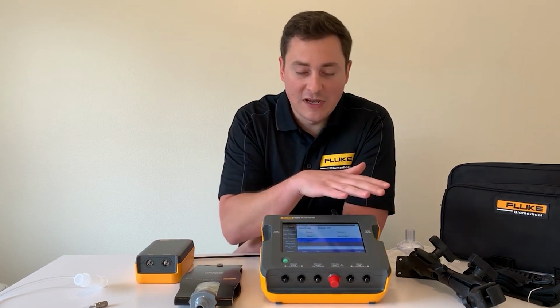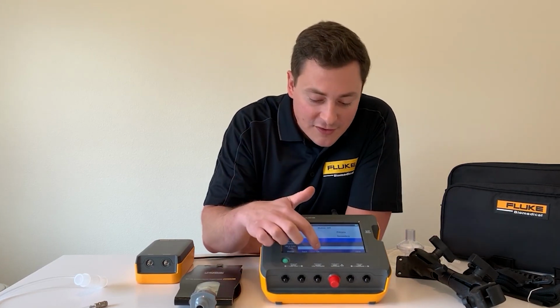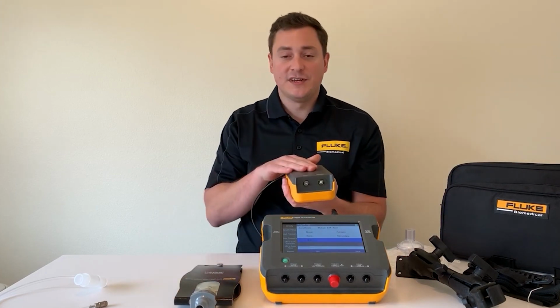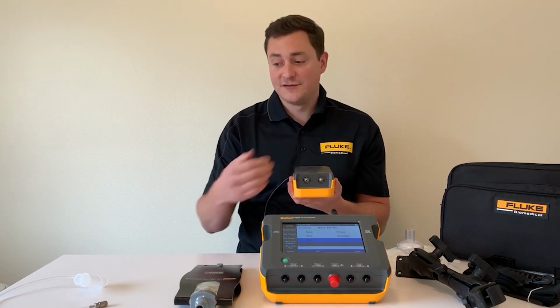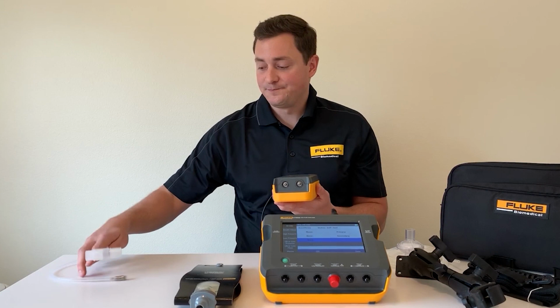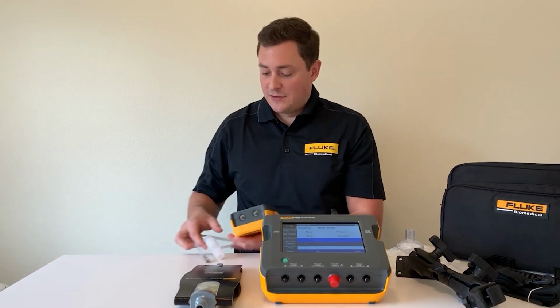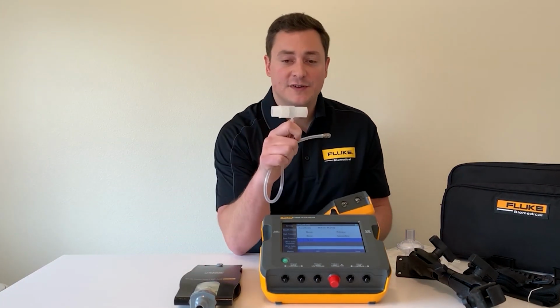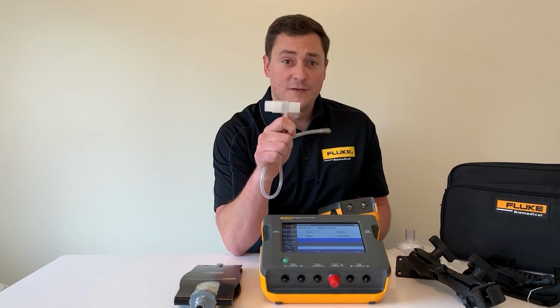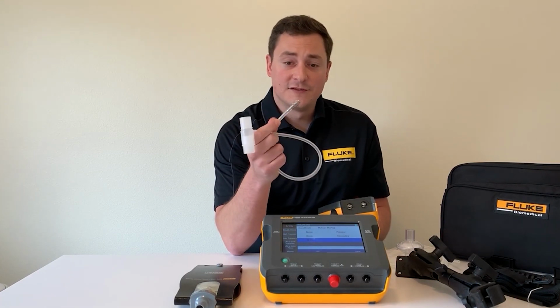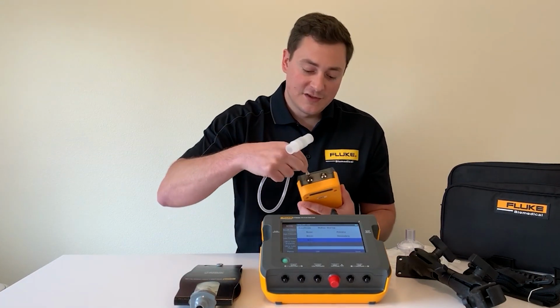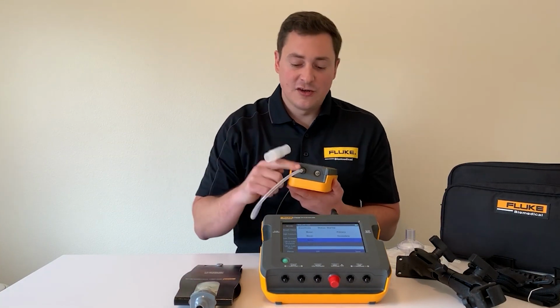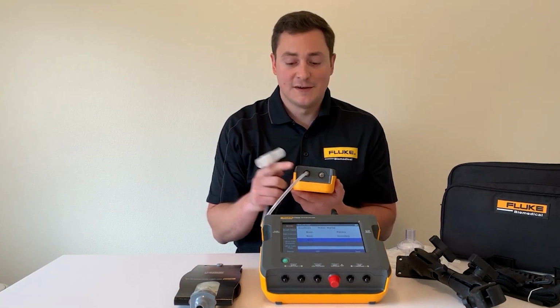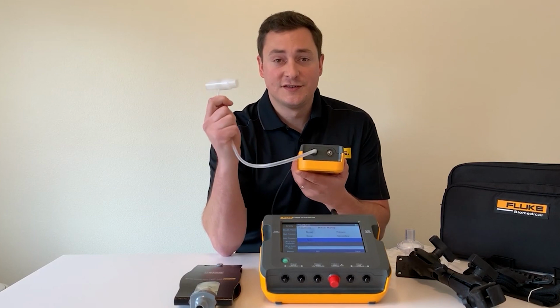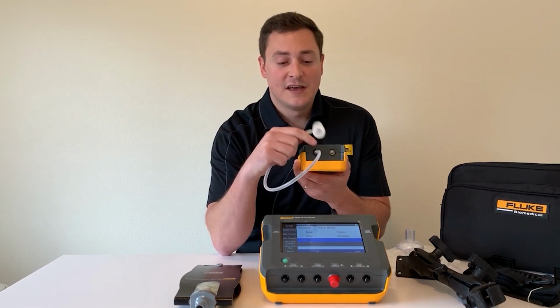So if we press that, we're now on the anesthesia screen, but you need to turn the unit on. There's a pump in here. It's going to pull from your mainstream because it's a side stream testing. So if we take this accessory that we get started with, it's a T, so it's going to pull from that mainstream, but we gave you guys a really nice connector here to make sure that you guys feel confident that you're not going to have any leaks. And this is just going to get you started. So it's going to hook up to your mainstream and you're ready to go.